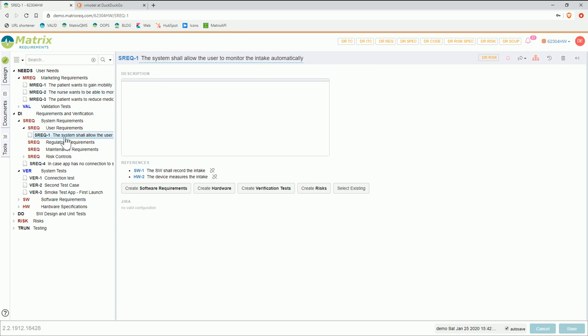For the system requirements it's a little bit different — here it's important that you actually think about what will be implemented later on, so here it makes sense to put in the details. You start with building blocks — you don't start a system requirement with the shape of a button in a user interface, but the system requirement is that the user can trigger a certain action. Then in the software requirements you can go into more detail.